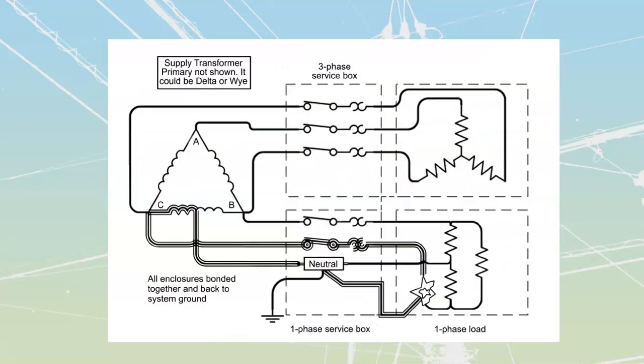This is going to give us two pathways for fault current. If we take a look at our single-phase loads over here, I'm going to have a single-phase load. If this thing grounds down right over here, so we accidentally connect it to the bond, what we're going to see is that we're going to deliver current from our load, it travels through the fuses, hits this, where it's got the option to go through resistance or not, and to instead go through this over here, my fault current path, which is going to be back along the bond, and back to the transformer.